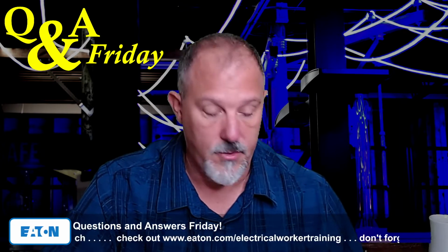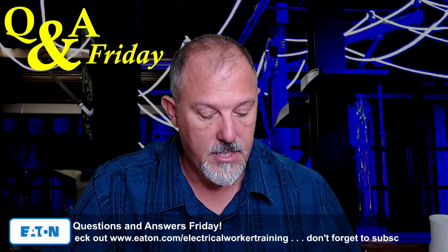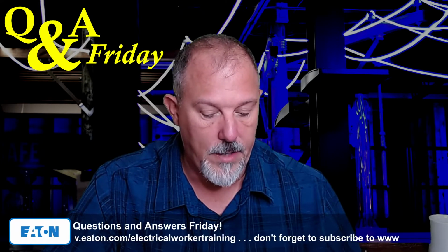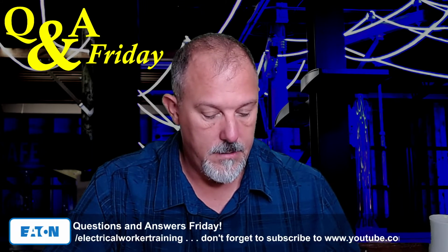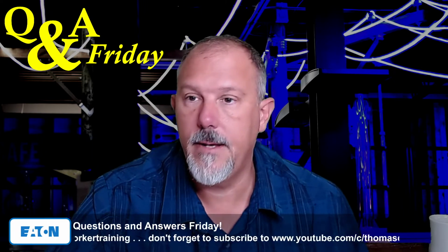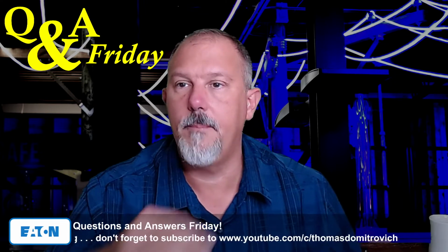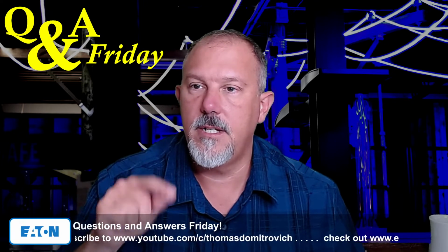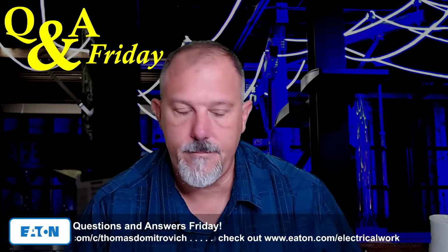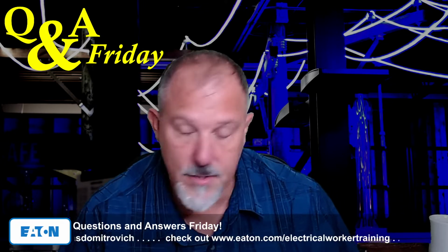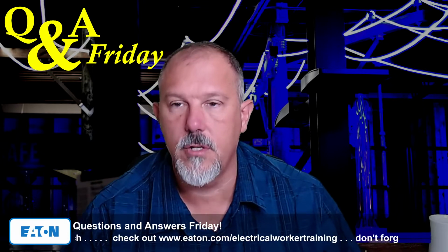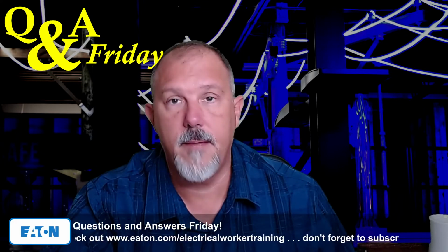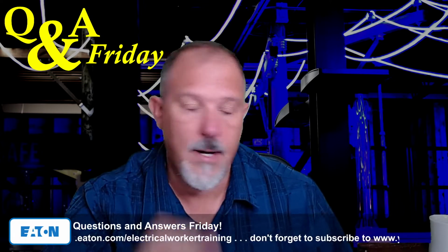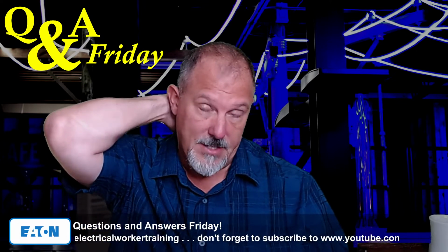And I don't agree that just because it says it's installed in a breaker, is rated or can be adjusted. I'm not sure where you're going with that one, JW. But turning a breaker down and sealing it to make it allowed doesn't necessarily reduce the additional heating on the trip unit if it operates at 100% of the setting. I don't disagree with you there. What I'd have to really do is look at the conductor size and the amount of current. So I really got to think about that one. That's a good question, though.